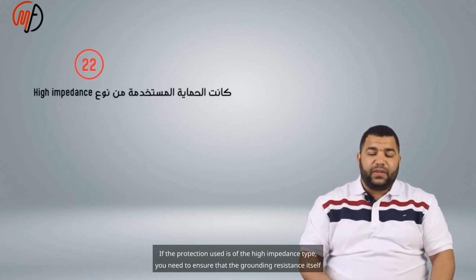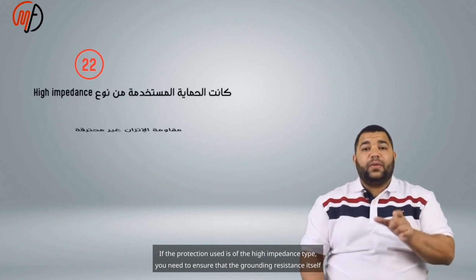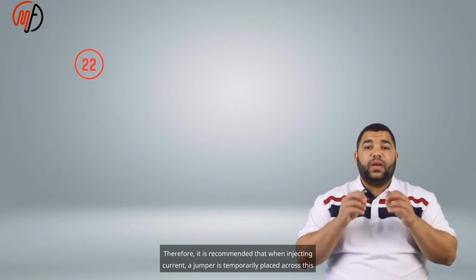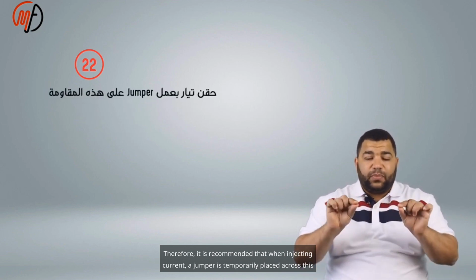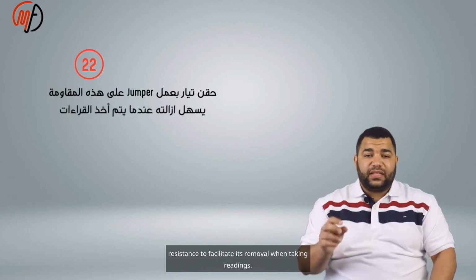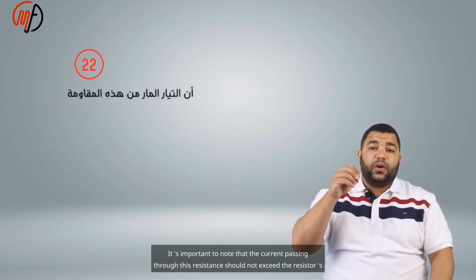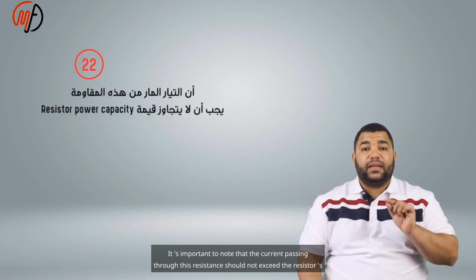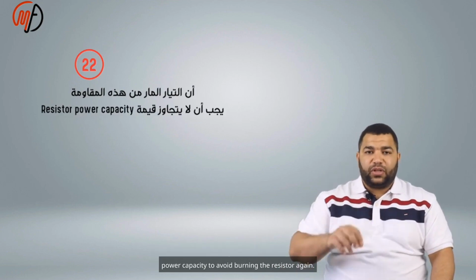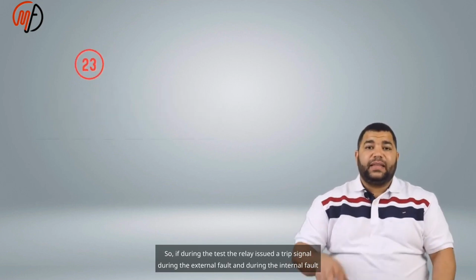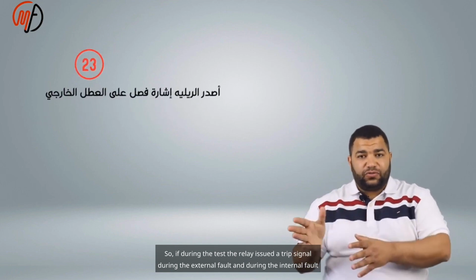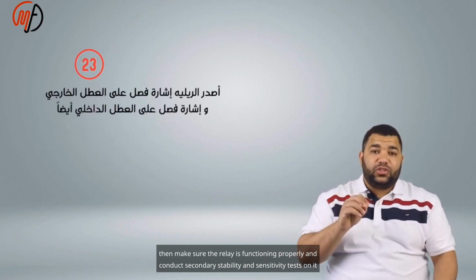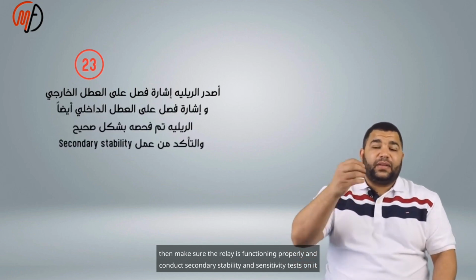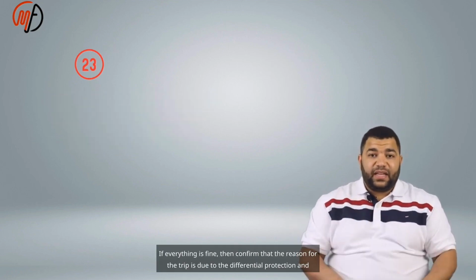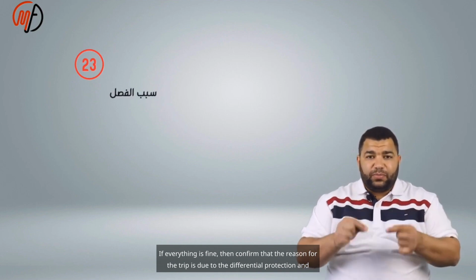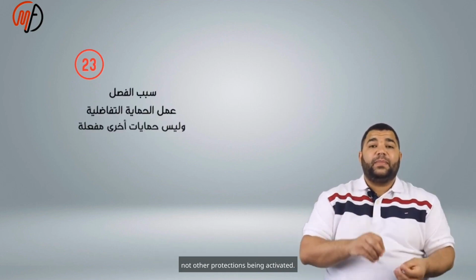If the protection used is of the high impedance type, you need to ensure that the grounding resistance itself is not burnt out. Therefore, it is recommended that when injecting current, a jumper is temporarily placed across this resistance to facilitate its removal when taking readings. It's important to note that the current passing through this resistance should not exceed the resistor's power capacity to avoid burning the resistor again. So, if during the test the relay issued a trip signal during the external fault and during the internal fault, then make sure the relay is functioning properly and conduct secondary stability and sensitivity tests on it again. If everything is fine, then confirm that the reason for the trip is due to the differential protection and not other protections being activated.